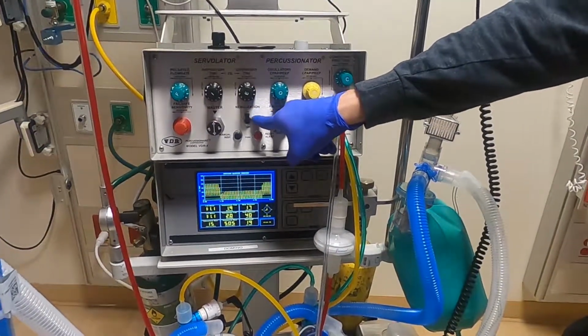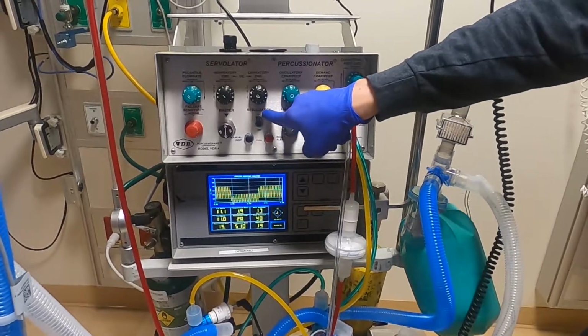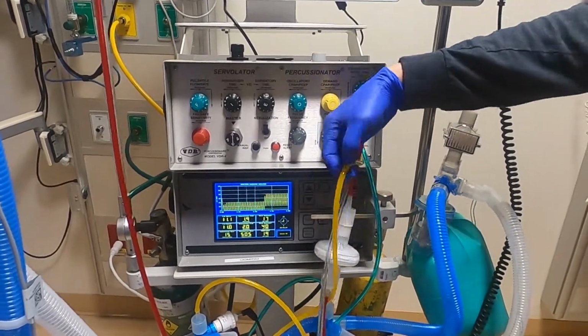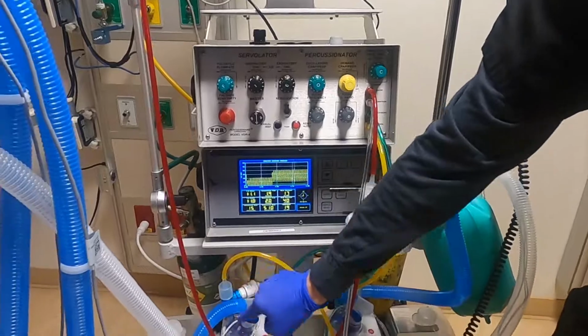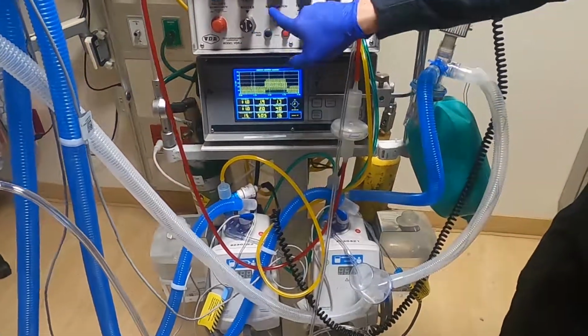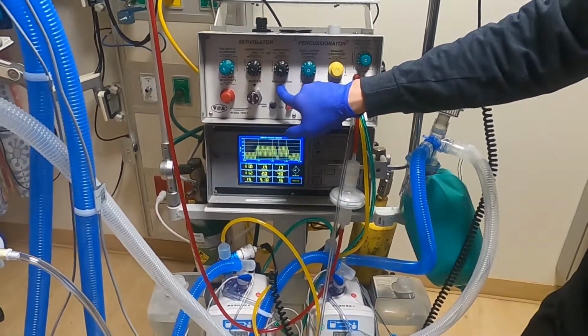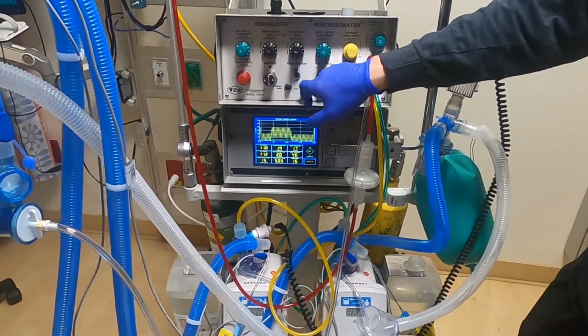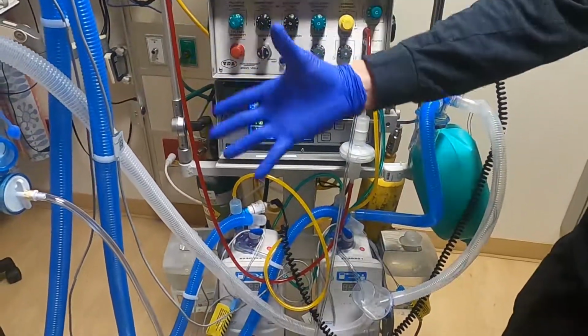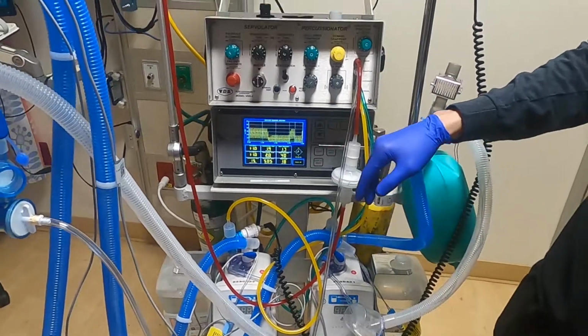This nebulizer switch is basically just adding flow into our humidification system. So you want to make sure that this is on. If you start the vent with it off and then you decide to add it on, it's going to change all of your vent settings because it's going to add more flow to the circuit.